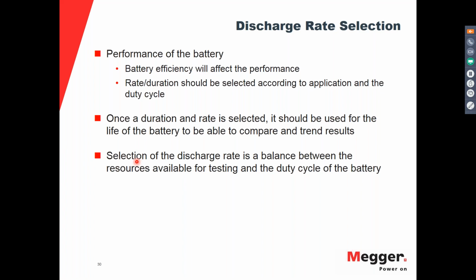The performance of the battery, when you do the rate selection, is going to be affected by the battery efficiency. And the other thing is that once a duration and a rate is selected, it should be used for the life of the battery. So for the test every 5 years, or whatever periodicity you select, you should run the test with the same rate. That is something to consider as well, that you are always going to need the same resources to be able to run that test, and that is going to affect your costs.